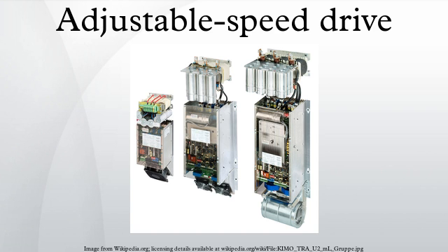For example, when a fan is driven directly by a fixed-speed motor, the airflow is invariably higher than it needs to be. Airflow can be regulated using a damper, but it is more efficient to directly regulate fan motor speed. According to affinity laws, motor-regulated reduction of fan speed to 50% of full speed can thus result in a power consumption drop to about 12.5% of full power.